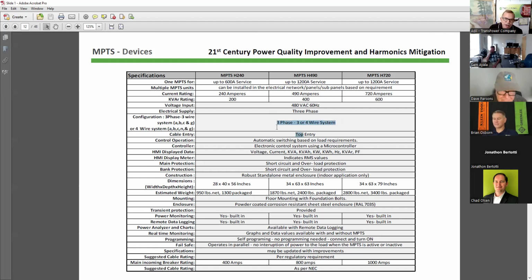The important question here is the 3-wire and 4-wire. Earlier the units were only 4-wire; they did not work on a 3-wire system. We started finding out, just like at Nevada Corrections or several customers we visited in California, Nevada, Arizona, and even Dallas, Texas, in brand new buildings, the designers are still building to old designs because the senior design electrical engineer has been in the field for 25 to 30 years or more. People get used to doing things the way they learned. So they're not paying attention to changes in buildings over the last 10 to 20 years. If you don't have a neutral and a ground in a building, you've already laid the foundation for a very expensive operating cost for that building.